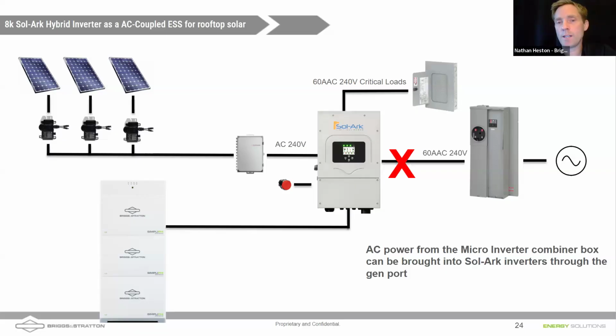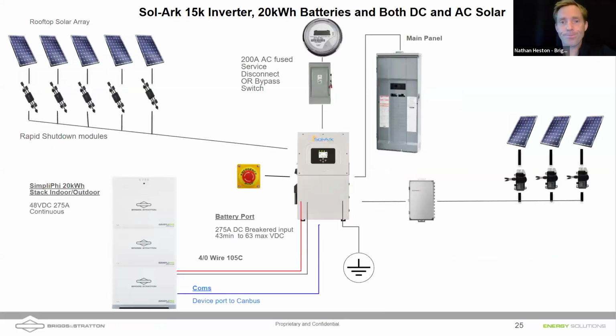Yeah, and that's a great point, Daniel. I mean, assuming that this initial installation was done properly, right, you would not be able to exceed, on a typical 200 amp service panel, as Daniel was talking about, 40 amps of backfeed current unless you, as he said, derated the main or upgraded the panel to having a larger bus, right, a bus capable of sending more back. But because we have PCS control in the Sol-Ark, you can always set a limit on that, which can avoid a costly panel upgrade, right?